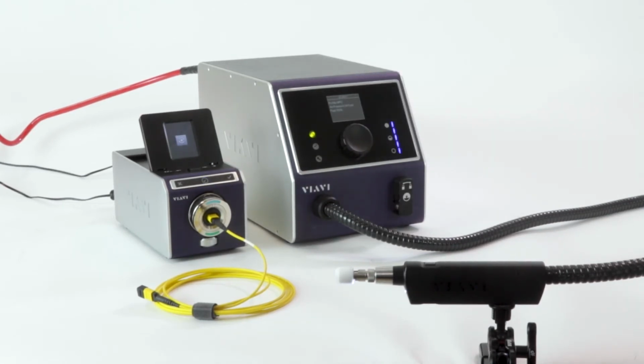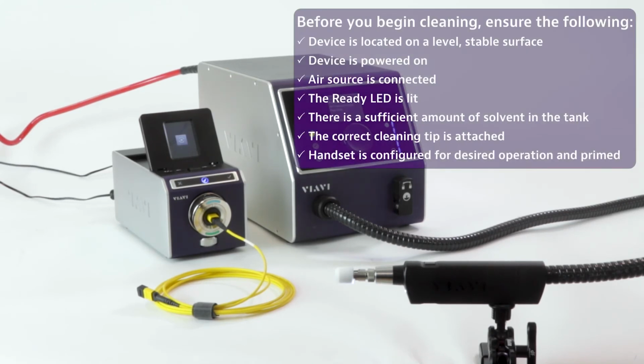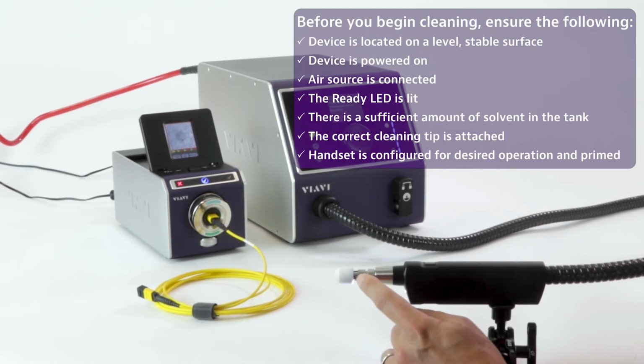While that's going on, I'm going to run through my checklist for my CleanBlast. Want to make sure that the device is stable and it's powered on. I'm connected to air, the LED is lit, and there's enough solvent in the tank. I've got the right tip and the handset. You can see here I've got an FCLT MTP tip as well as the MTP-MA mating adapter for cleaning the patch cord, and my handset has already been primed.